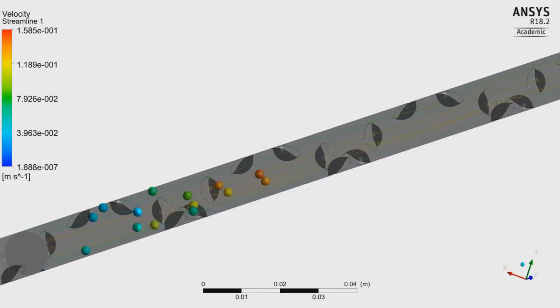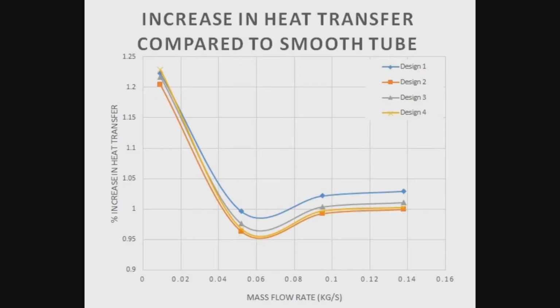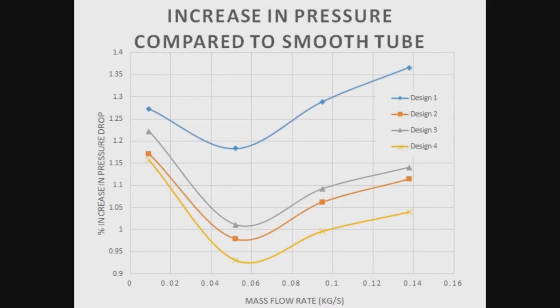CFD simulations were run for all tubes at 4 different flow rates ranging from laminar to turbulent flow conditions. The dimpled tubes proved to increase the heat transfer through swirling the fluid and mixing the cold outer layer with the hot inner layer of water. The most significant increase is during laminar conditions. The maximum increase in heat transfer was 22%, with a pressure drop increase of 37%.